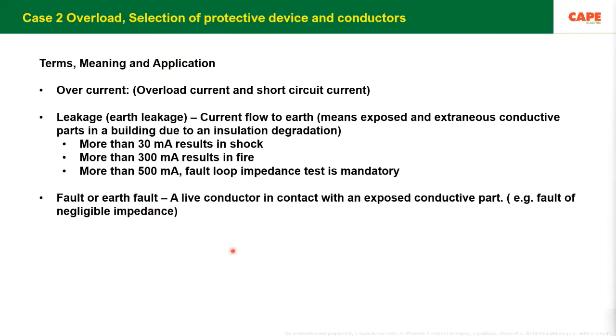Similarly, the third one is called a fault. Short circuit happens between current carrying conductors, between phase conductors or between phase and neutral conductor. But an insulation failure between a current carrying conductor and the earth is called a fault. It is also called an earth fault. It means a live conductor is in contact with an exposed conductive part. That means the impedance, the resistance between the live conductor and the earth, meaning the body of the equipment, is quite low. As a result, a person touching it may get electrocuted, may get a shock. So basically, overcurrent, leakage, and fault are three distinct safety measures. We should always keep this in mind and select the appropriate protective measure.